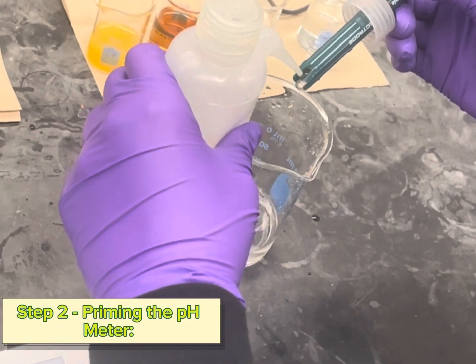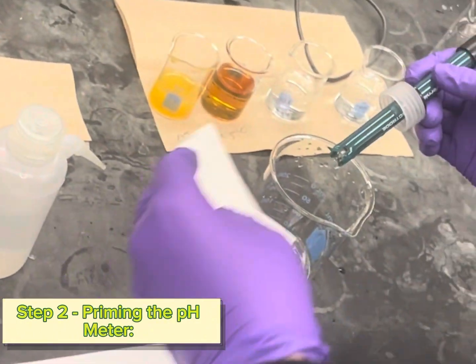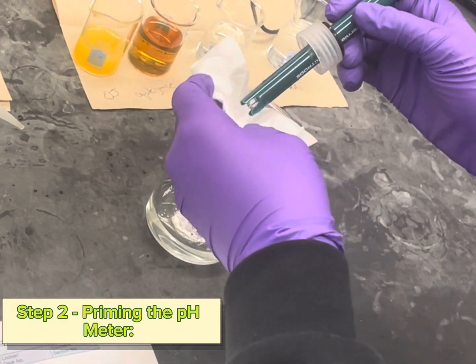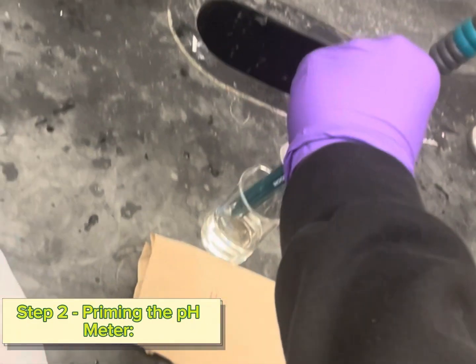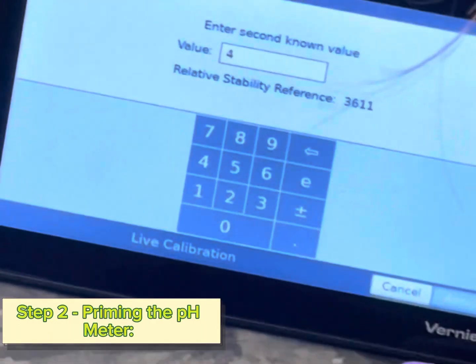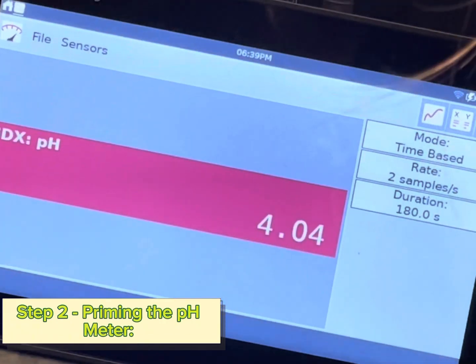Now you're going to repeat the same process but with the pH 4 buffer solution. Clean your pH meter with deionized water, wipe it with a Kimwipe, and place it gently in the pH 4 buffer solution. Return to the screen, type in 4, wait for it to stabilize, and select Keep. And you should be taken to this screen.